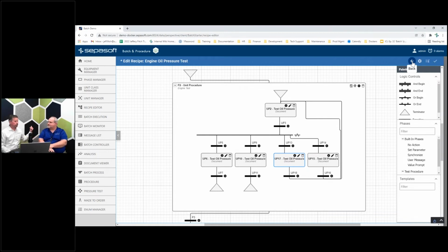That script might issue an alert on the ignition alarming, or I could tie that in with a tag, either way. So if you have a longer running script though, maybe it goes to the ERP system, gets the next serial number. Maybe it goes to a database and does a call, or a web service call, or does a complex calculation. You can have a script phase in here, and the engineer can set up that script. The recipe author can just drag it over, drop it on the screen, pass in the batch parameters to that script. The script can process, so it can pass data.